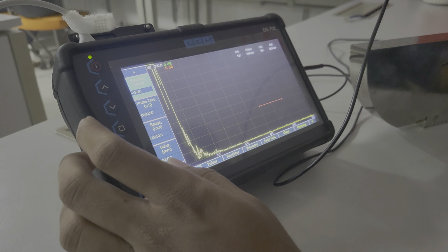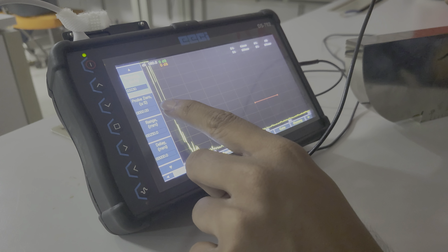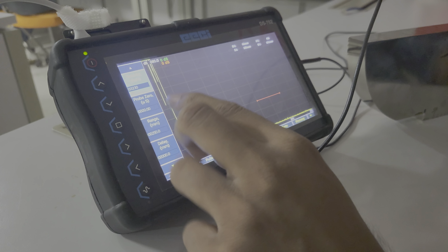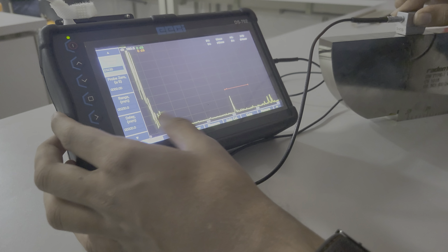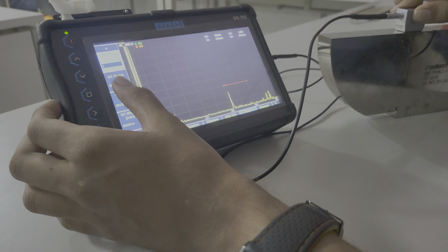and as we go into the base, we have set probe 0 as 0.00 to check the initial peak at the highest peak level. So first we will keep here, and we need to adjust the gate also. We will keep the gate like here.